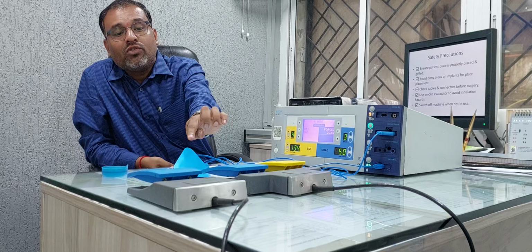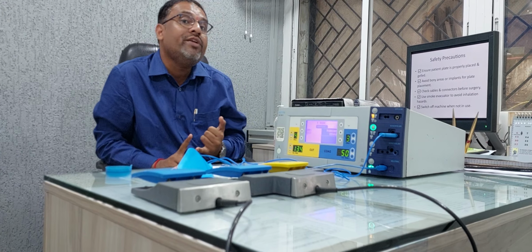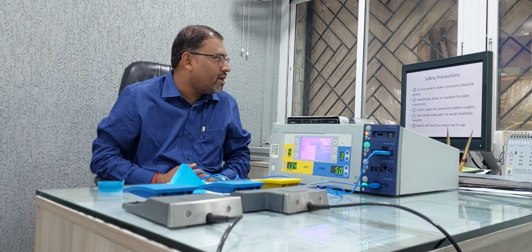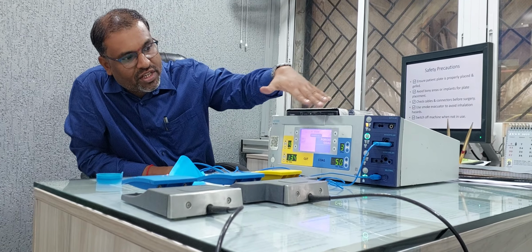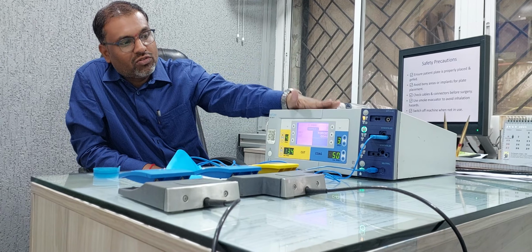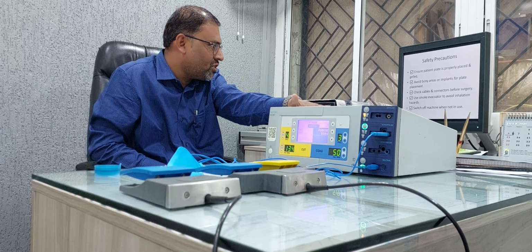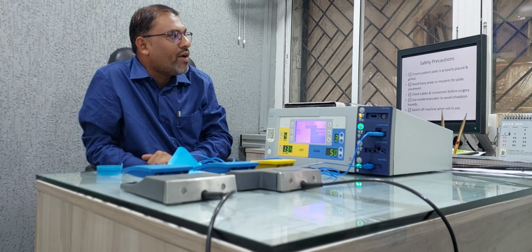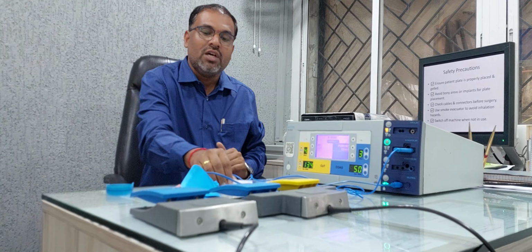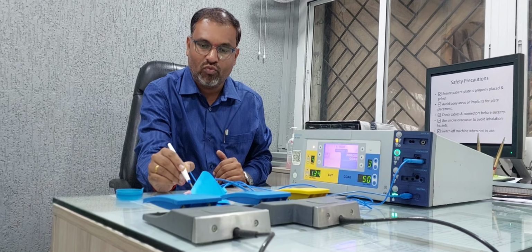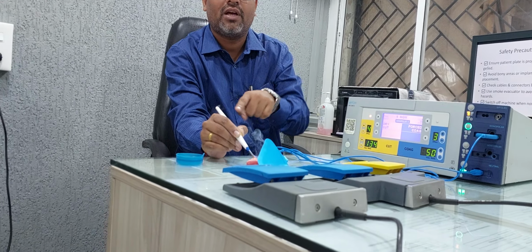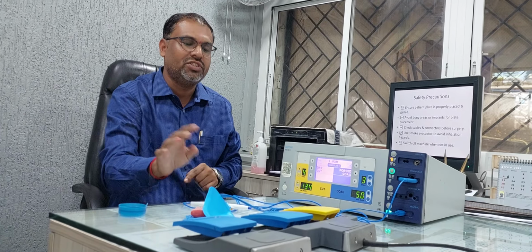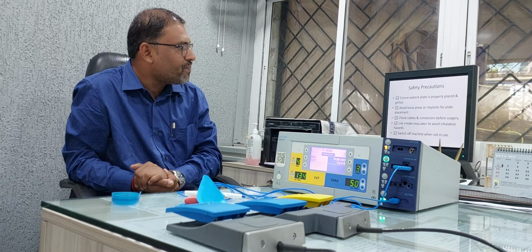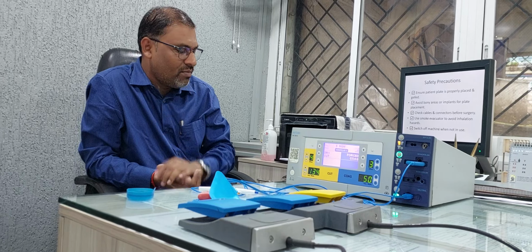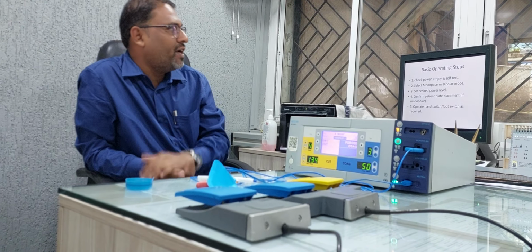Second, when you are going to connect such patient plates, avoid bony areas, right, and implant areas. Third, check cables and connectors before surgery. Check if there are any indications on the machine or any red alarm on the machine, right? And always use a smoke evacuator to avoid inhalation, because when I cut the tissue, what happens? It will create a lot of smoke, and that smoke is harmful to the surgeons. So you have to use a smoke evacuator for that. And when the machine is not in use, always remember it should be in a switched-off condition.